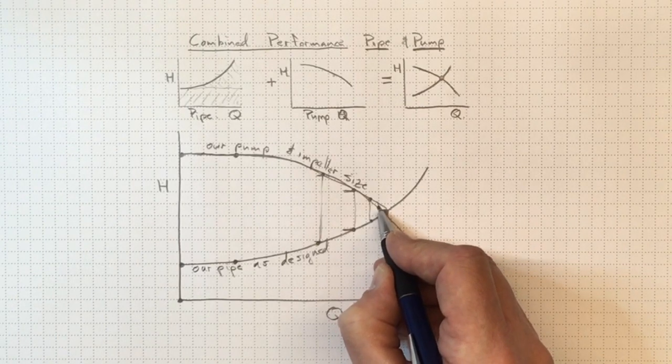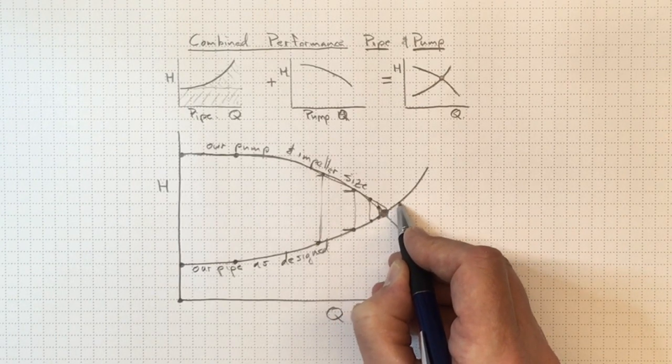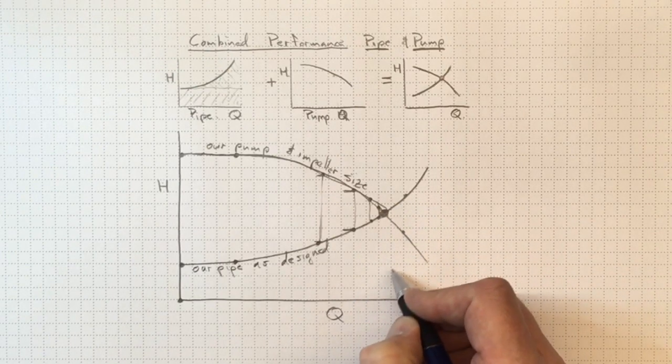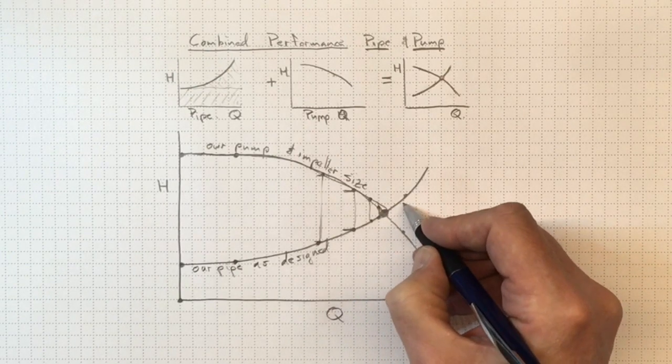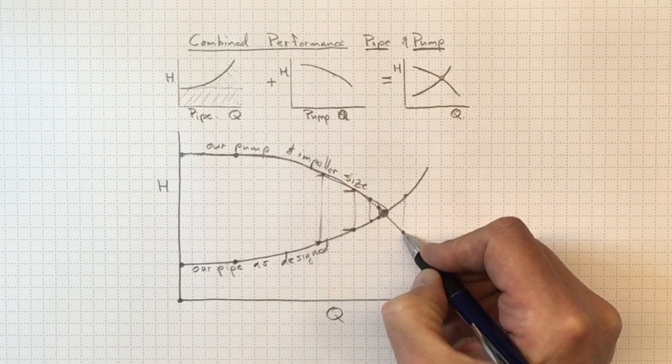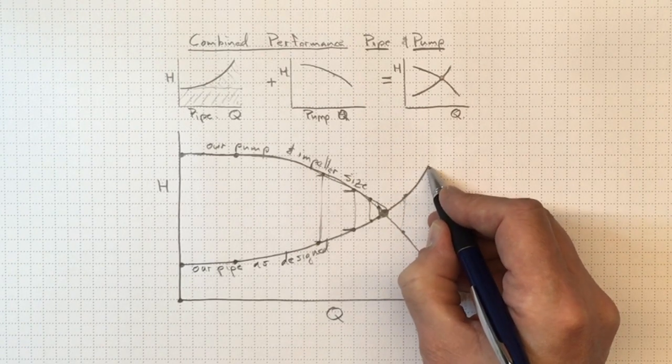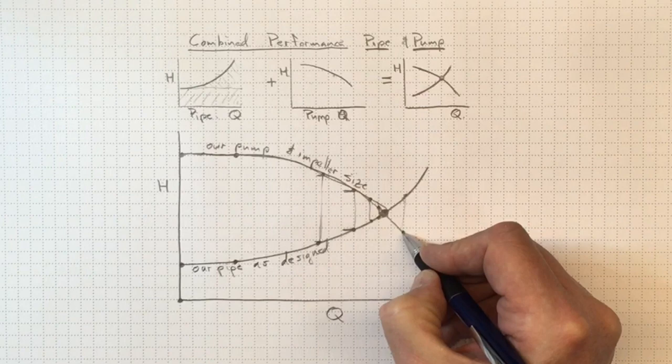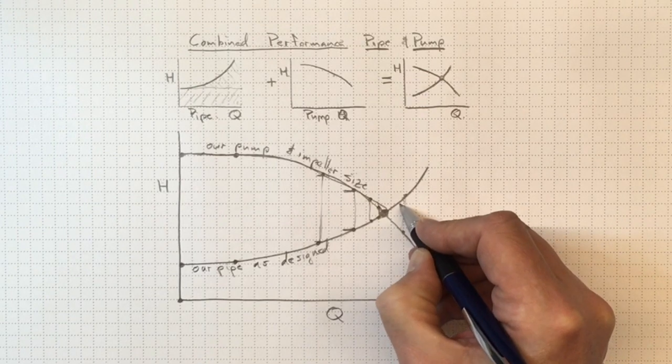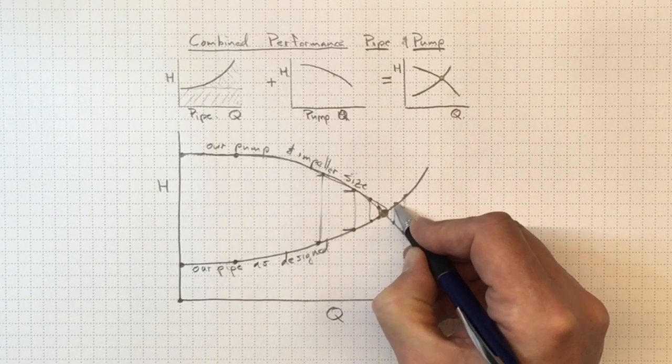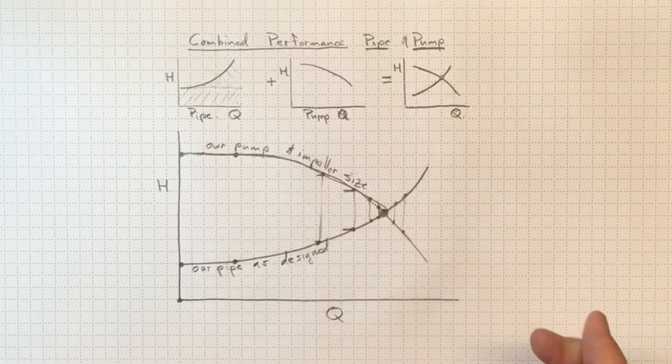Now of course if we were accelerating and somehow we managed to get out to that operating point, and I can't really picture quite how, we'd have the inverse difference. The losses are now much higher than what the pump is putting in and the flow will tend to move stably back towards this operating point.